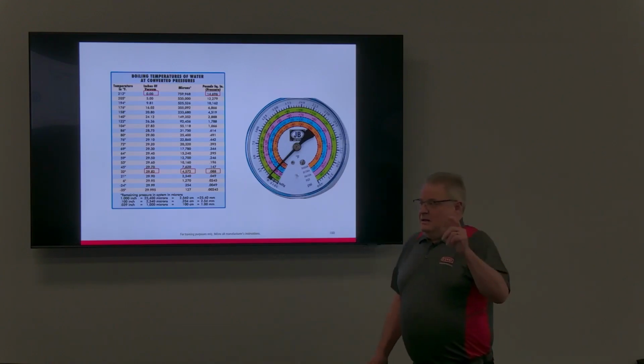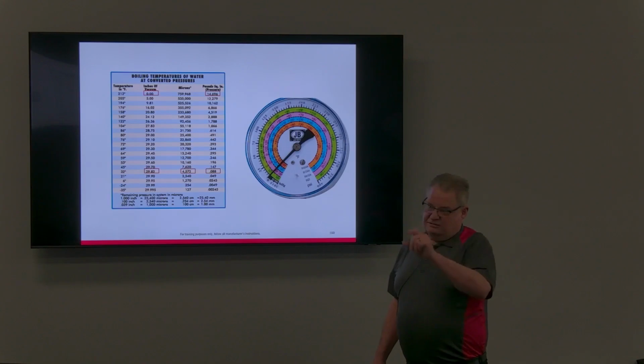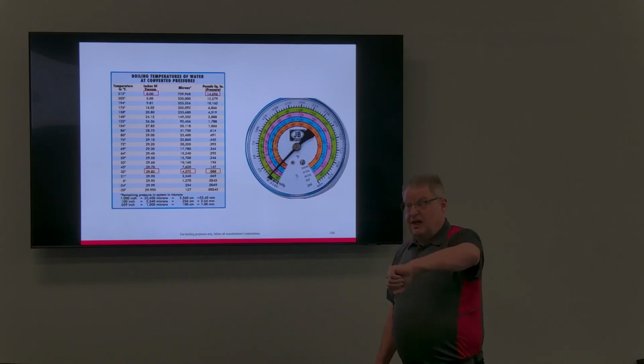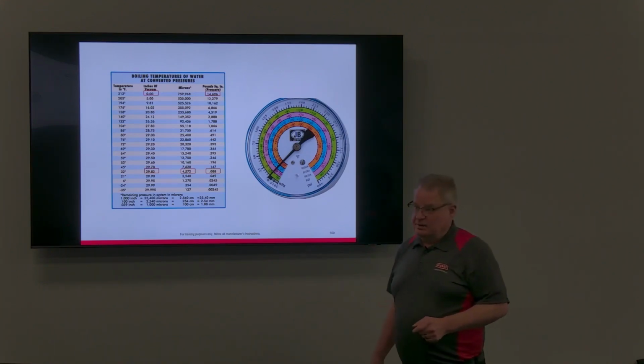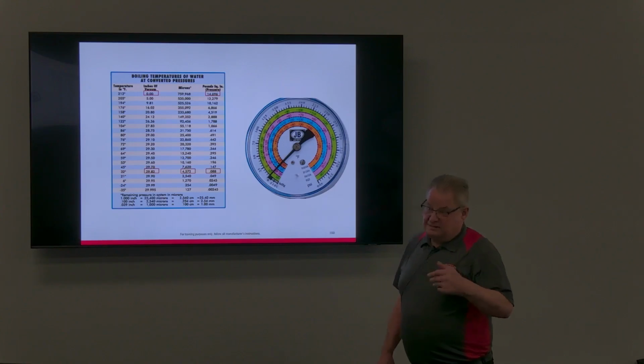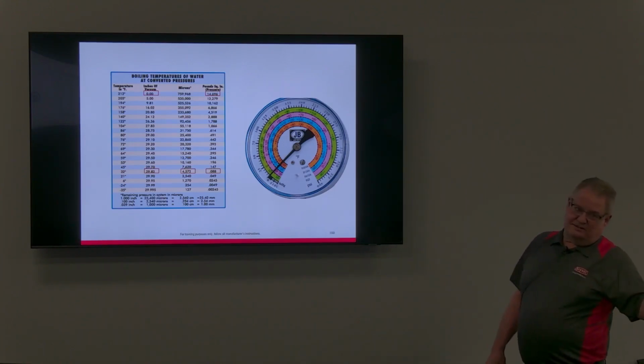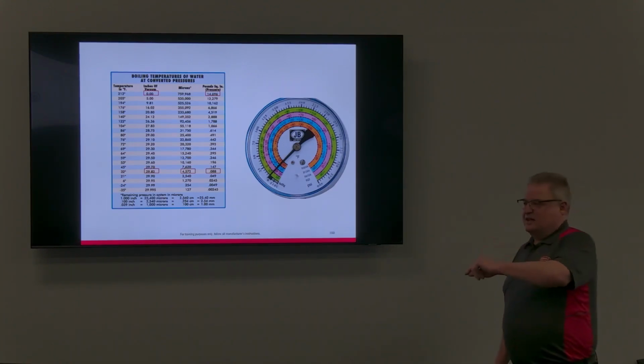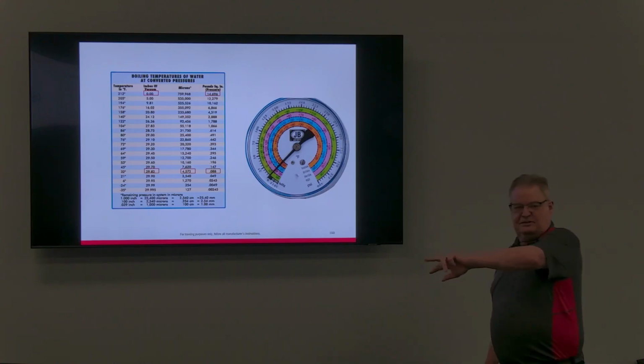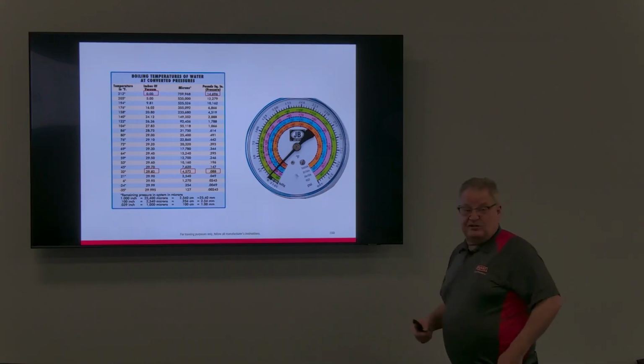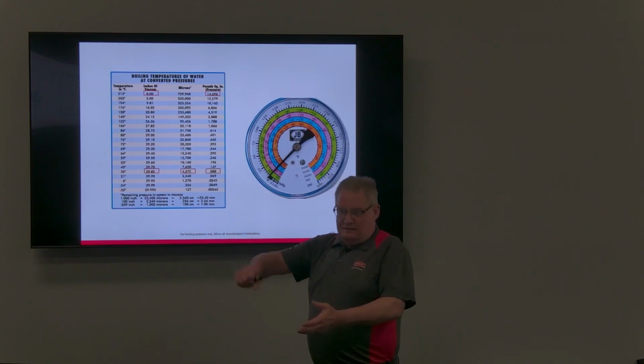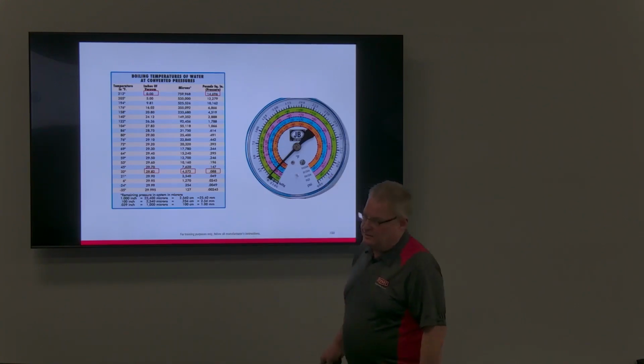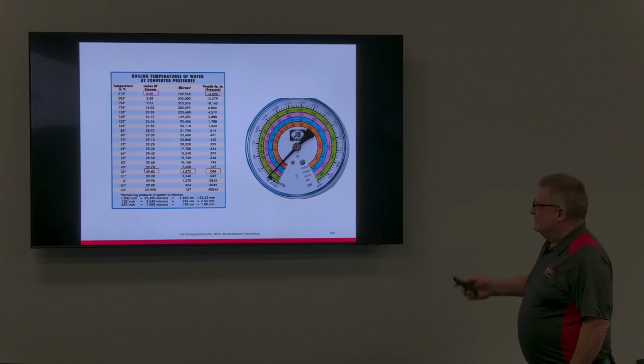Okay. One of the methods I've been kind of sold on, everybody see that gun we sell, shoots some little rubber plugs? Not by itself. You pour some flush, and then you use that rubber plug and blow it through a couple times. The combination of the two is funny, because the company that makes the plugs says theirs are the greatest, and the flush guys say, oh, that sucked. Then they say the flush is no good. Actually, I've seen it work really well with both. Not a whole bottle of flush. You just pour some in there and then shoot them pigs, they call them pigs, back and forth. But clean that line set out.